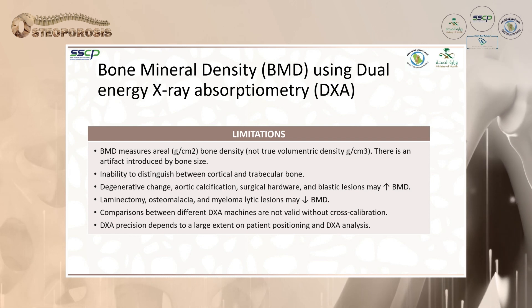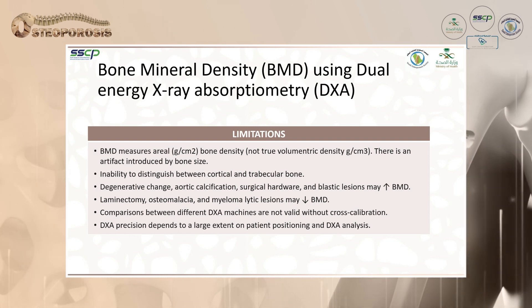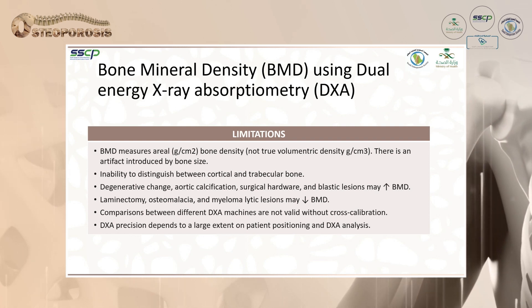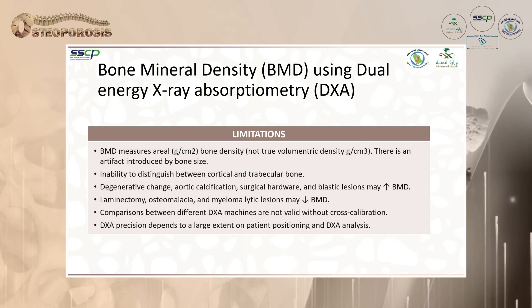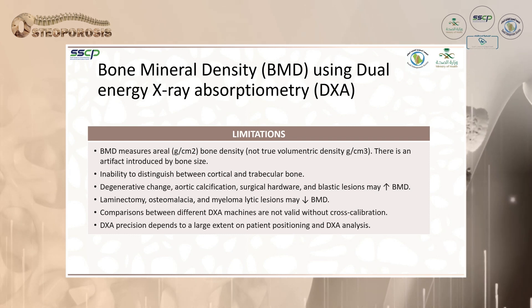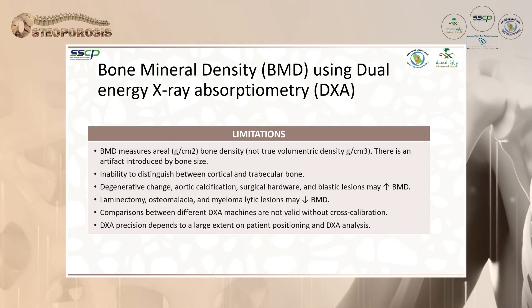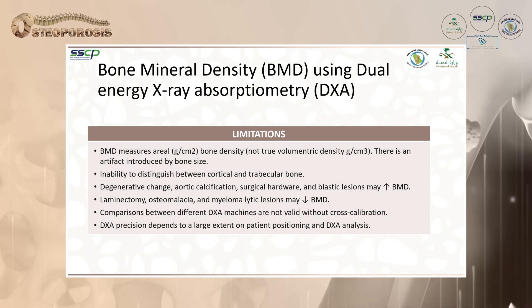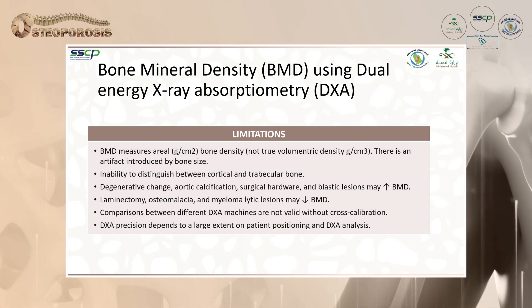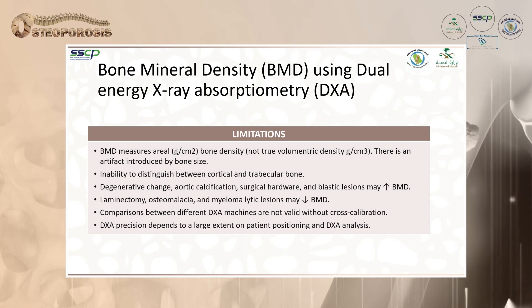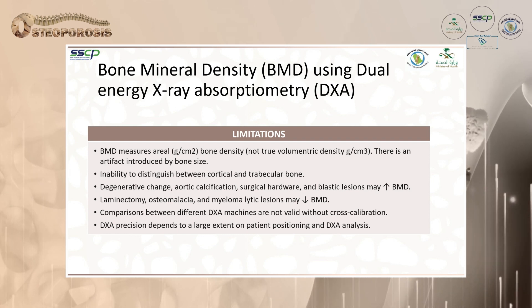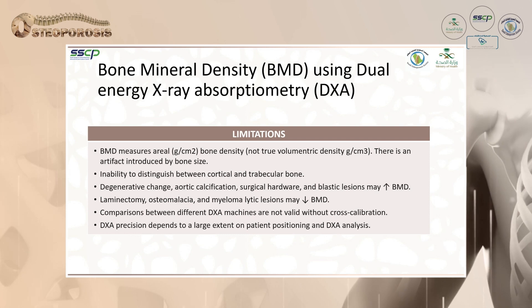DEXA limitations include that it measures area density in grams per centimeter squared, not true volumetric density in centimeters cubed, and there is artifact induced by bone size. Degenerative changes, aortic calcification, surgical hardware, and blastic lesions may increase BMD, while laminectomy, osteomalacia, and multiple myeloma may decrease it. Comparison between different DEXA machines is not valid without cross-calibration, so it is best to repeat scans on the same machine. DEXA precision also depends largely on patient positioning and analysis.